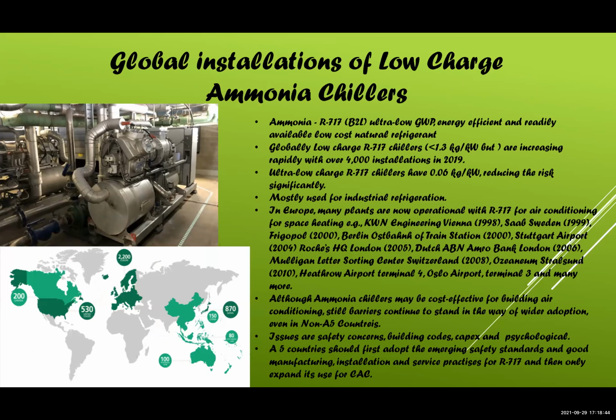In the world, particularly Europe, it's going in a big way using ammonia. That is because ammonia is a very efficient refrigerant. But as Omar said, it's a B2L. That means it's not only low flammability, but also toxic. So it's one of the few refrigerants which are classified as toxic. R123 is B, and then ammonia is another. Very few refrigerants, you can count on the fingers of one hand, are B class. Most of the refrigerants are A class, non-toxic. But ammonia is a B2L. It has ultra low GWP, close to zero.